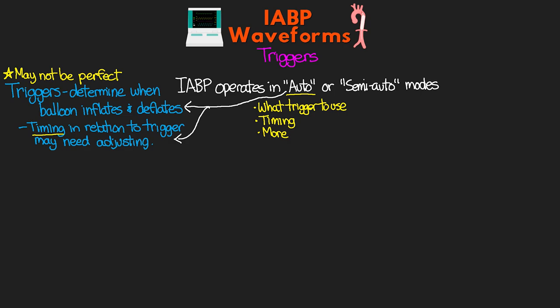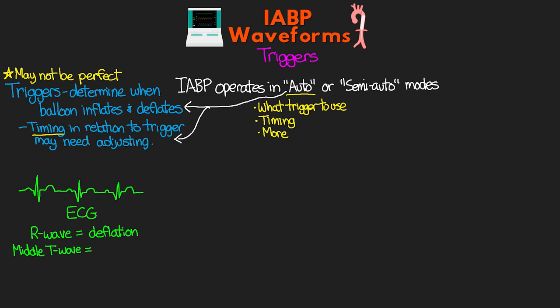There are a few ways to trigger the balloon pump. First and preferably is our ECG trigger. The balloon pump reads the ECG tracing and uses certain trigger points to initiate inflation and deflation. The R wave is our trigger for deflation — the heart is beginning to contract, so we want to deflate the balloon. The middle of the T wave is the trigger for inflation, as this roughly corresponds with when the aortic valve closes and we are in diastole.